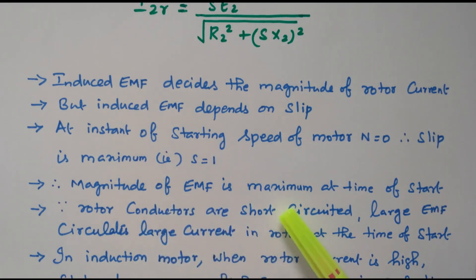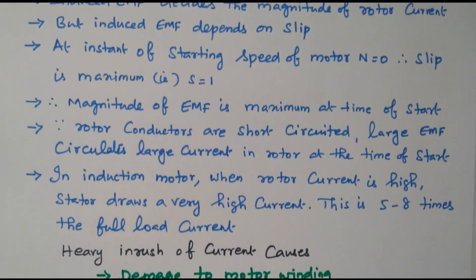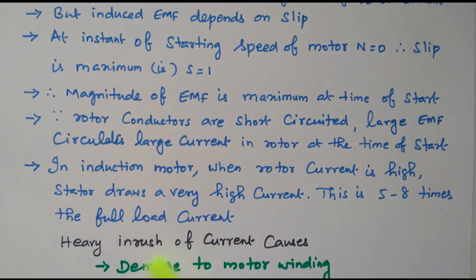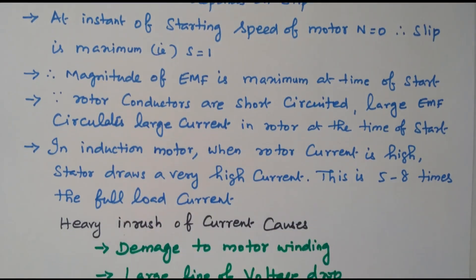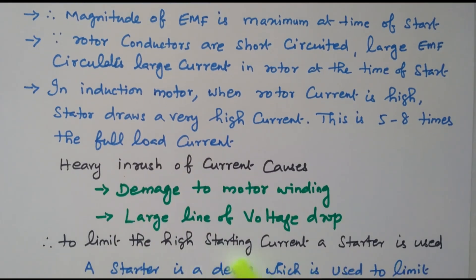The magnitude of the induced EMF is maximum at starting, so the rotor conductors are short-circuited and large EMF circulates large current in the rotor. In an induction motor, when the rotor current is high, the stator draws a very high current — about 5 to 8 times the full load current. Due to this inrush of high current, it may damage the motor winding and cause a large line voltage drop. To limit this high starting current, a starter is used.